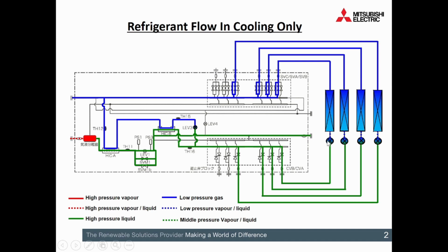As it gets within 2 degrees of set point, we start backing down those expansion devices, giving yourself that individual control. And then you're going to end up with more and more, so we say, flash gas. Therefore, you're going to get higher and higher superheat at the end. But normally, if this is running as a flooded evaporator, I'd expect to see 0 to 4 degrees of superheat. So it's literally running as flooded evaporators. As it gets within 2 degrees of set point, I'd expect that to be near to maybe 10 to 15 degrees superheat. So the idea was we're doing trim work at that point.